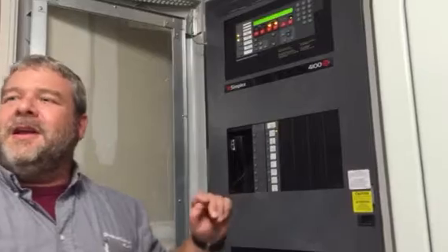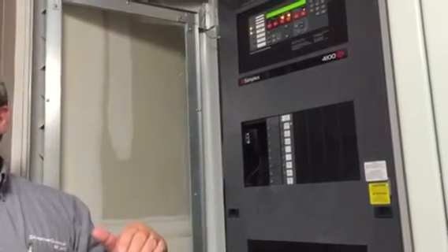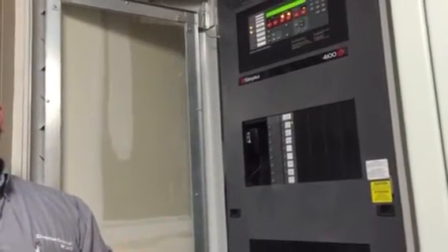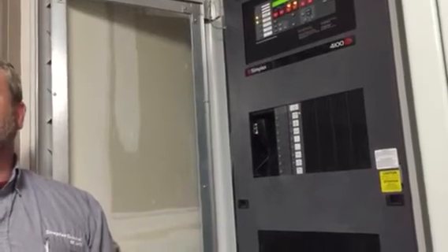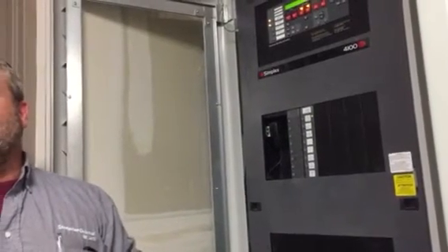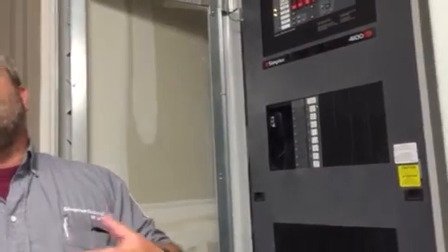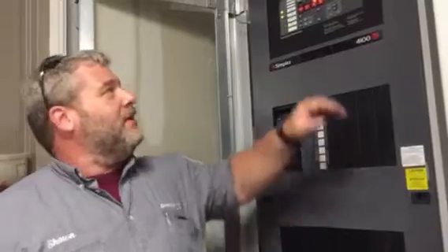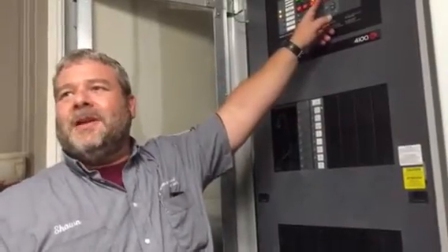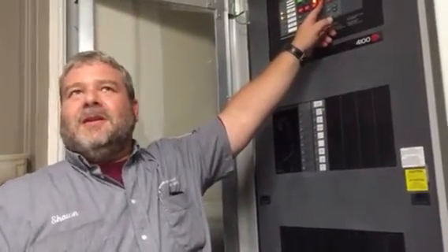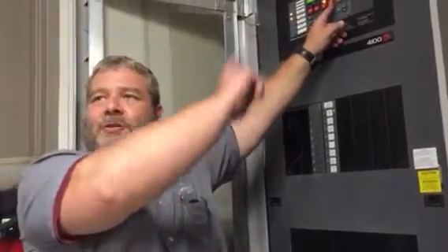There are sets of batteries in both of those. The panel does monitor those batteries. Those batteries are typically good for about 3 to 4 years. Sometimes they'll go 5. But by code, they need to be replaced every 4 or 5 years, or upon manufacturer recommendation. All manufacturers say 4. If those batteries start to go low, it will cause a trouble. It'll come in and tell you low battery, and it'll tell you which one it is.